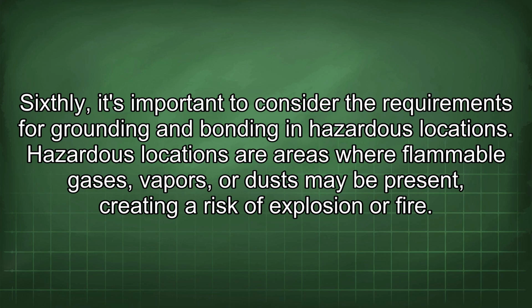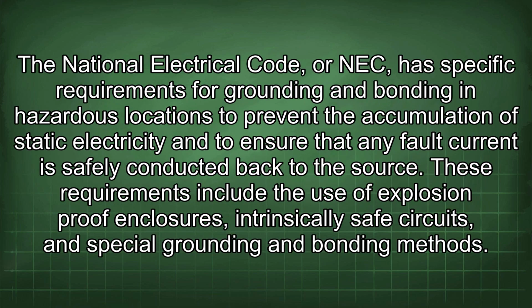Hazardous locations are areas where flammable gases, vapors, or dust may be present, creating a risk of explosion or fire. The National Electrical Code, or NEC, has specific requirements for grounding and bonding in hazardous locations to prevent the accumulation of static electricity and to ensure that any fault current is safely conducted back to the source. These requirements include the use of explosion-proof enclosures, intrinsically safe circuits, and special grounding and bonding methods.